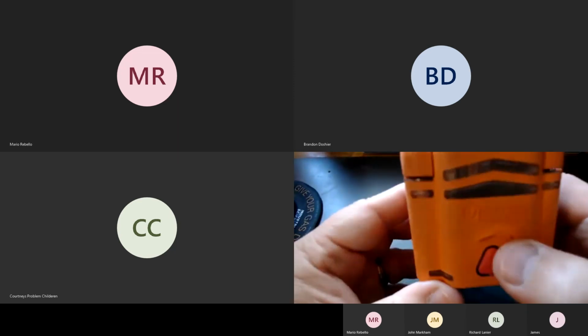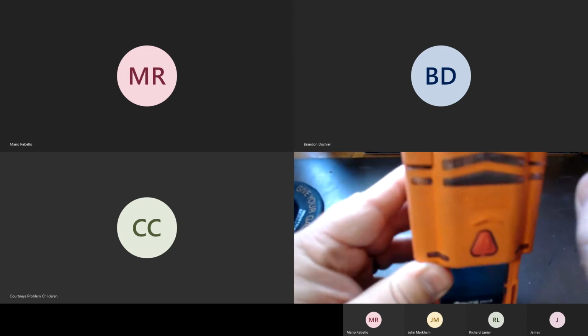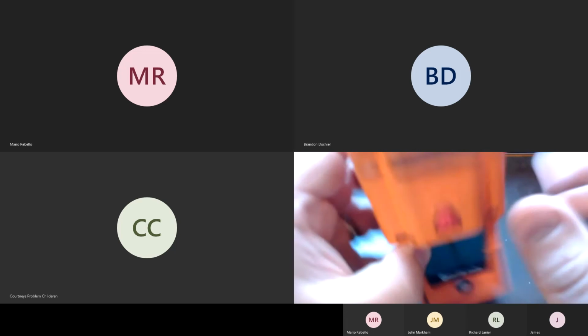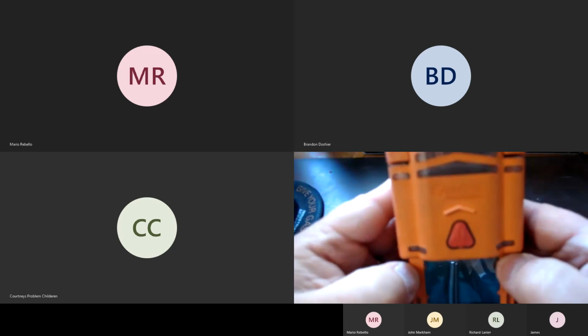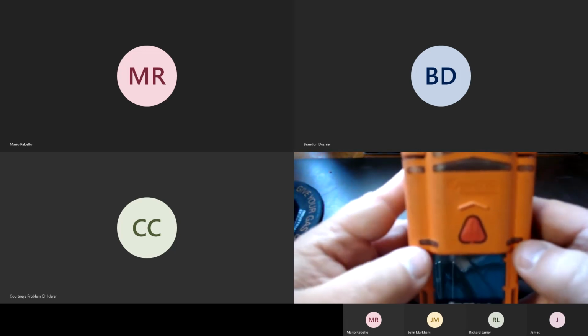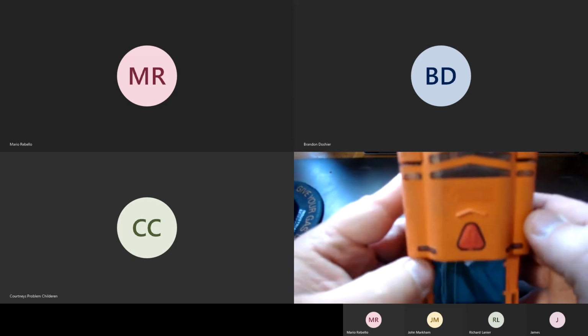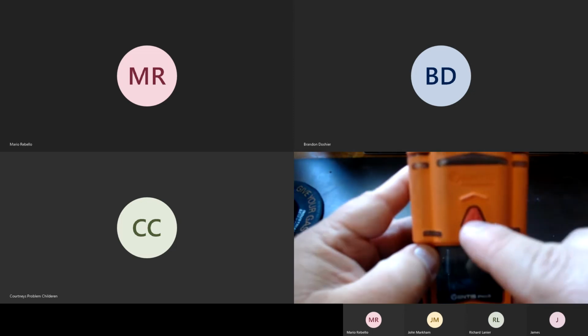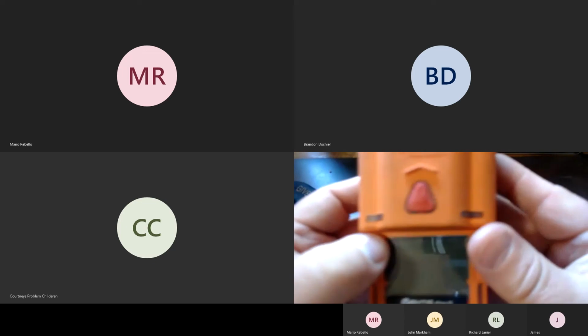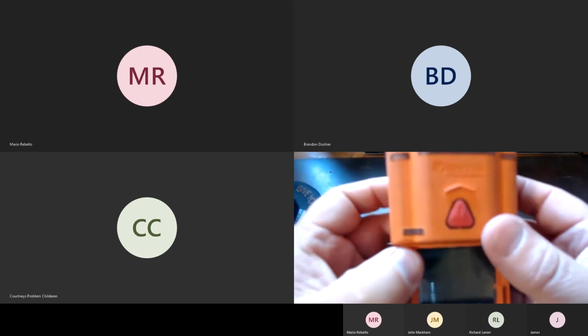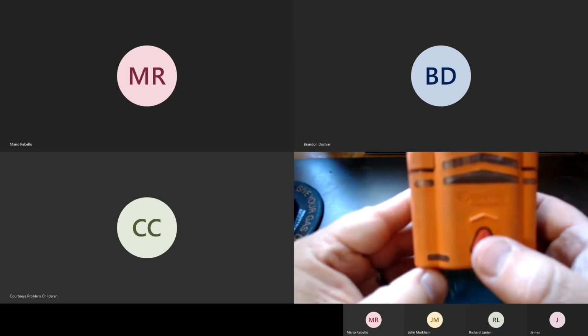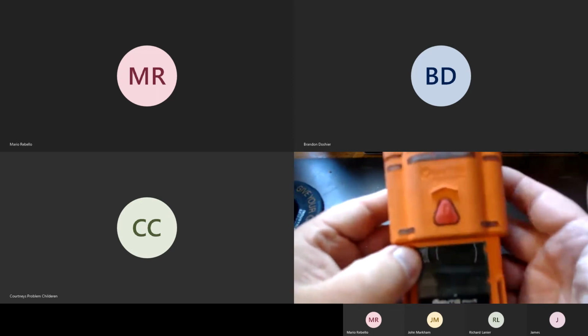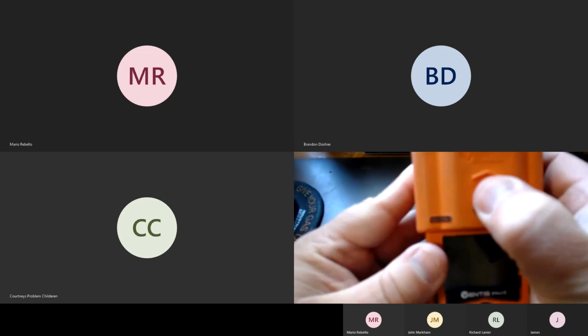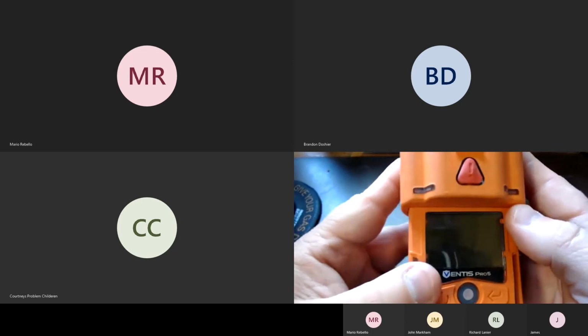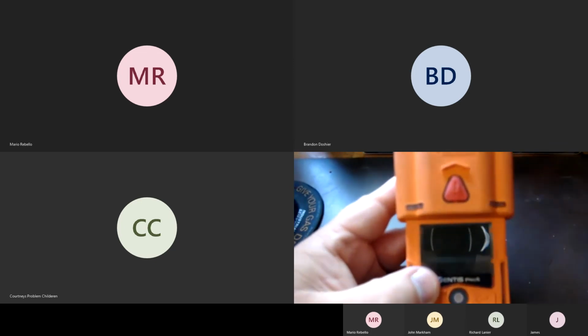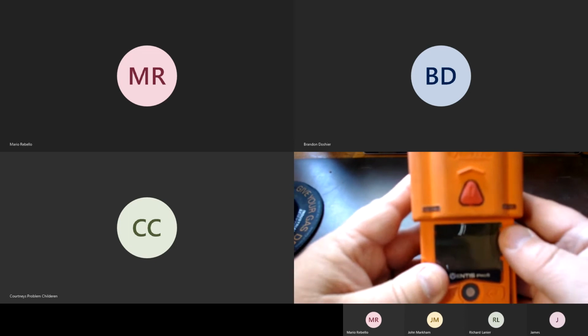All right, so as we come down, all these little cutouts are here for lights. Just LEDs so you can see what's going on with the instrument. These ones right here are blue, these ones are red, and right here in the center we have a panic button. That panic button is just like the panic button on your PASS device. You press and hold that to activate it. Same thing here. You press and hold this for 3 seconds when the instrument is turned on, and it will activate a panic alarm, and it'll just start screaming and calling for help.